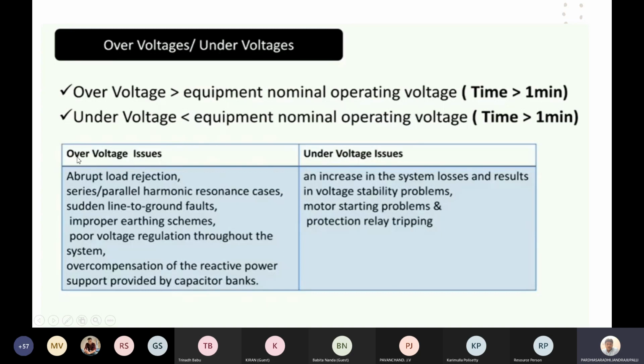As we already know, the difference between over voltage and under voltage may be due to sudden load changes. Particularly, over voltage is due to abrupt load rejection, suddenly, if any load is removed. Other causes are series parallel harmonic resonance cases, sudden line to ground faults, improper earthing schemes, poor voltage regulation throughout the system, and overcompensation of the reactive power support provided by the capacitor banks. So if more capacitance is added in order to compensate the dropped voltage, instead of acting as a voltage regulator up to the rated voltage, the voltage keeps increasing, right? Whereas under voltage issues cause an increase in the system losses and result in voltage stability problems, motor starting problems, and protection relay tripping. So these are the various reasons for the over voltage and under voltage problems.